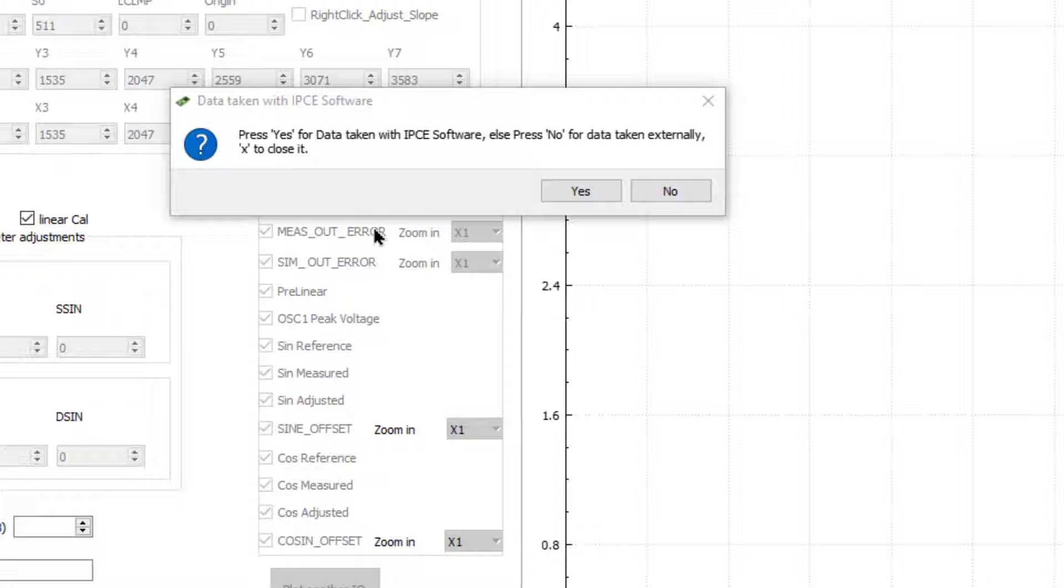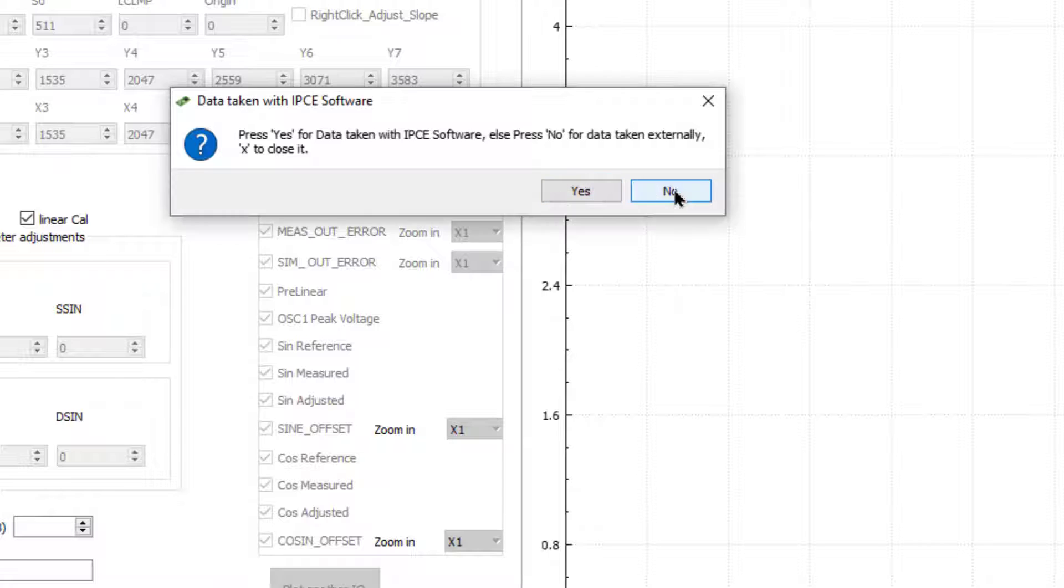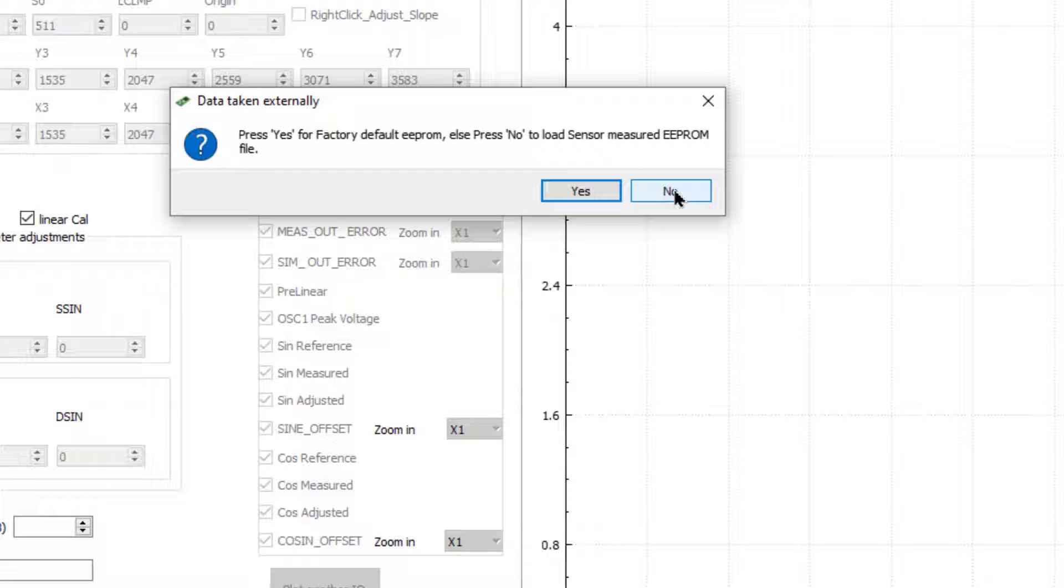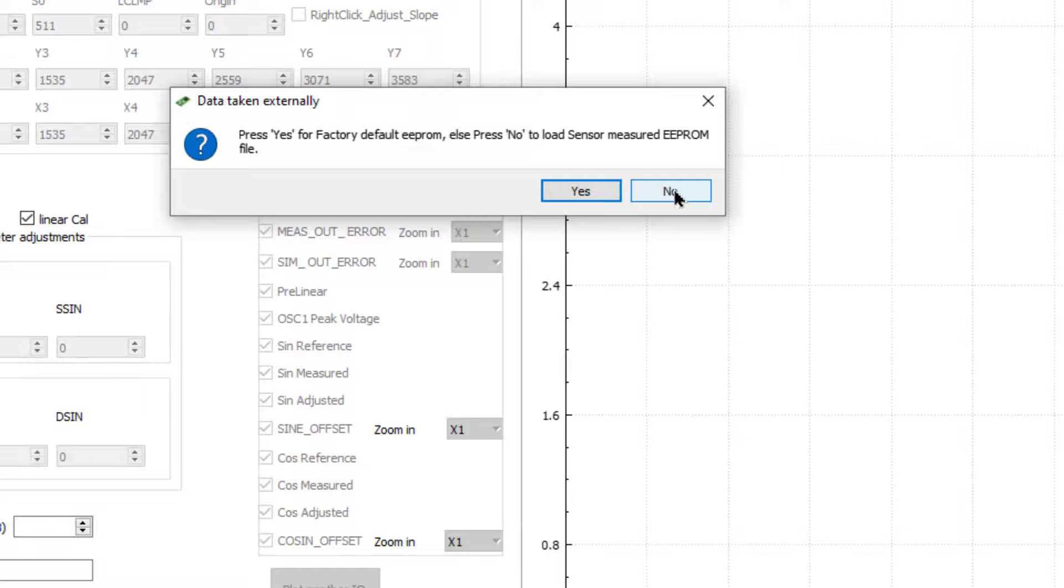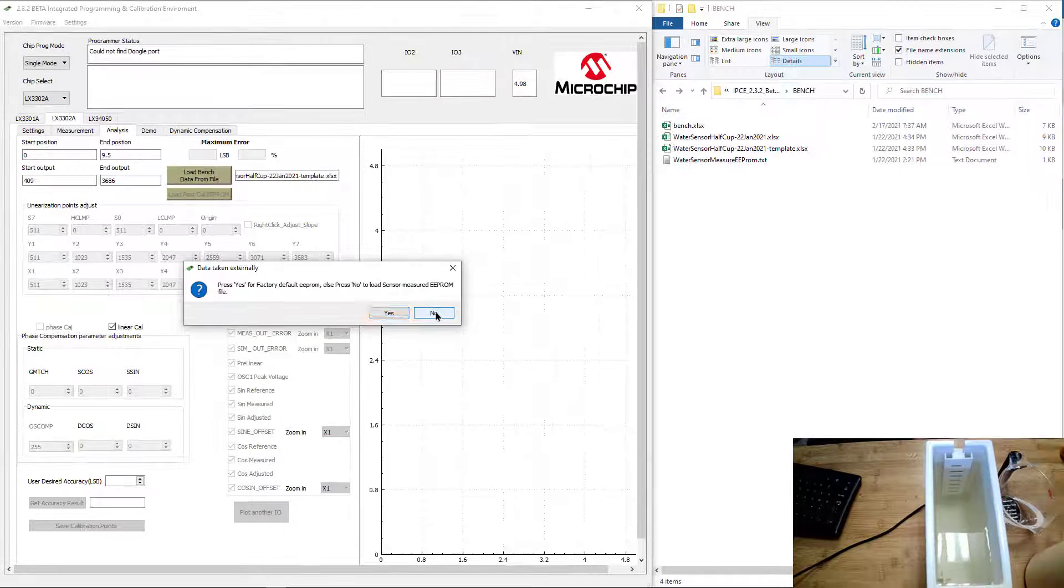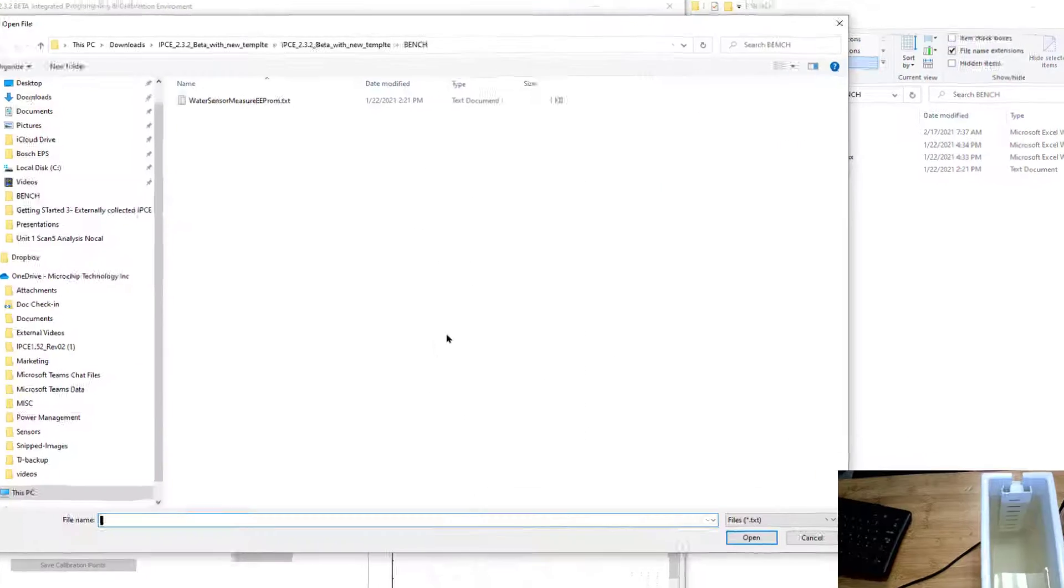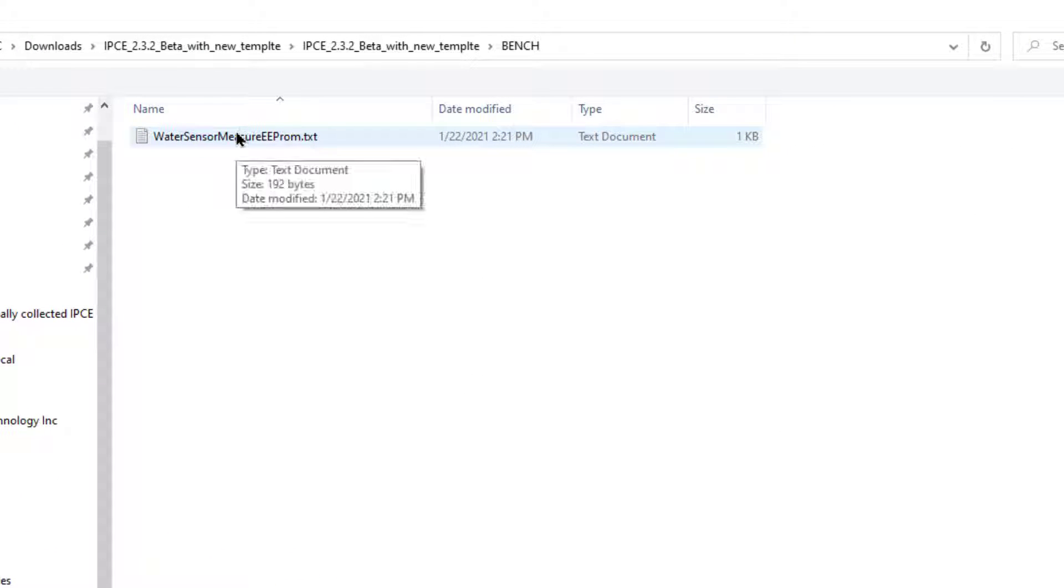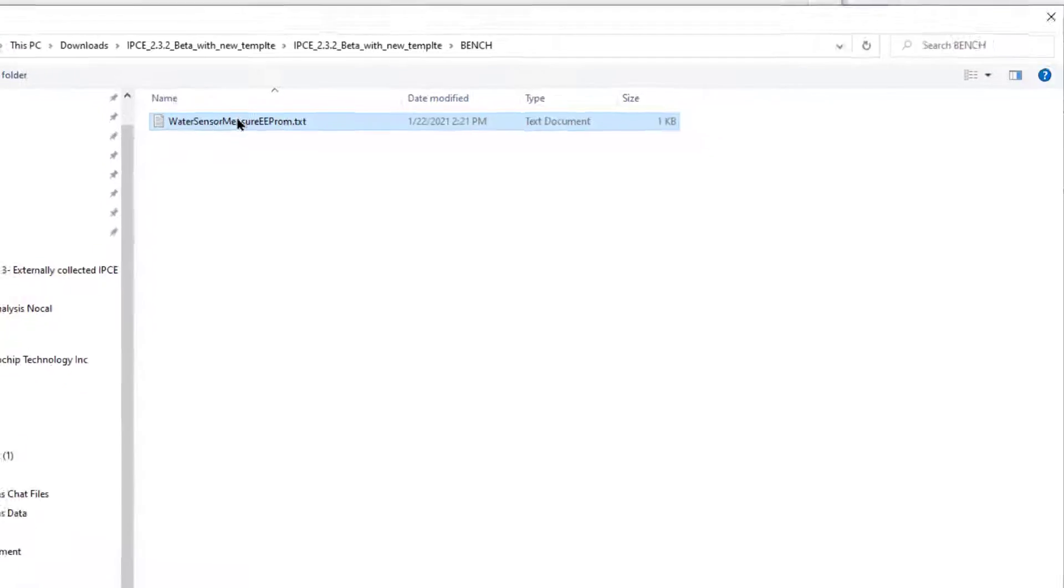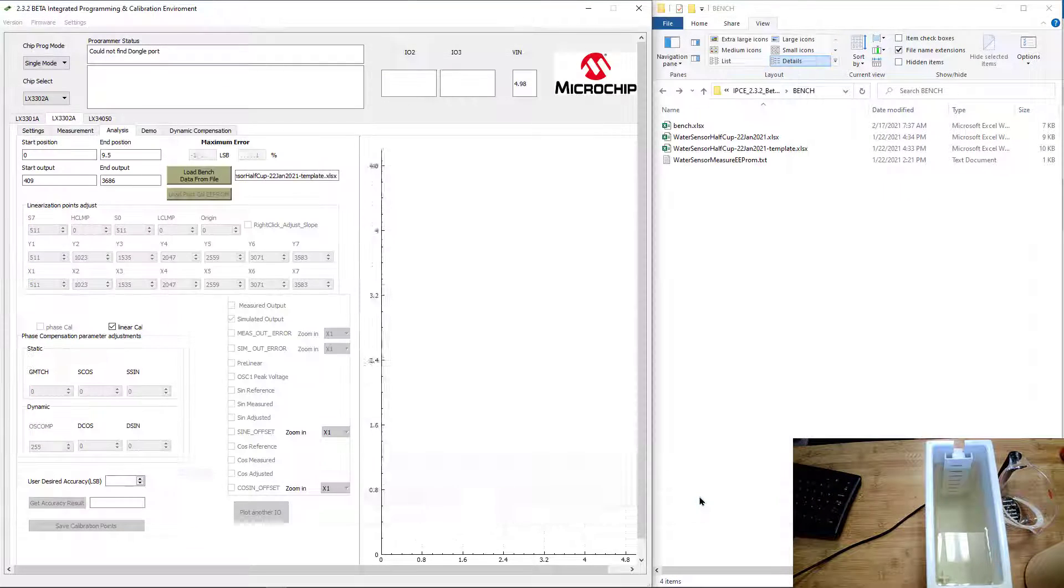If you did take it with the IPCE software, it will also keep track of the calibration points that you used or the EEPROM values when you took the data. In this case, we're taking it externally, so now we're going to have to load those EEPROM values into the system in addition to the data points. When you click no here, it's going to ask what type of EEPROM values did you use when you took the measurements? We're using the default value. In our case, we were not. When I took the data, I was using another set of calibration points that I had saved. I'm going to hit no here and load those calibration points that I used when I measured the sensor.